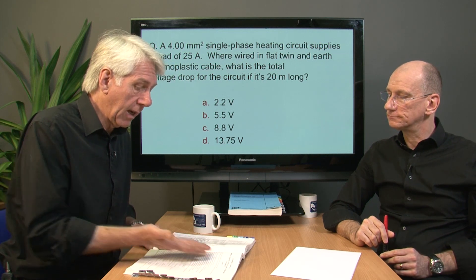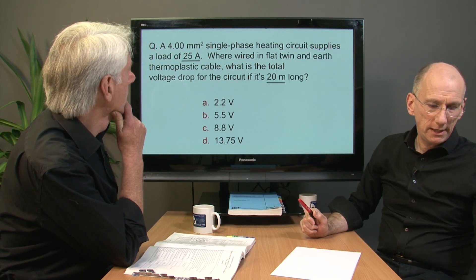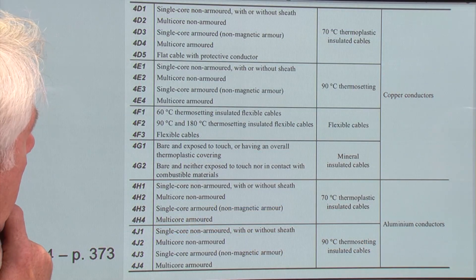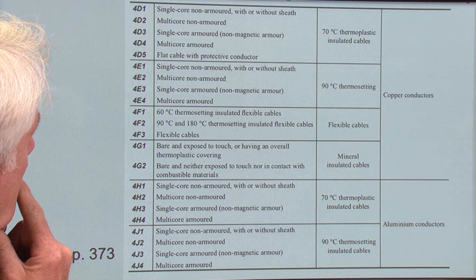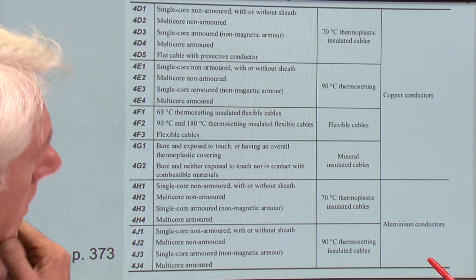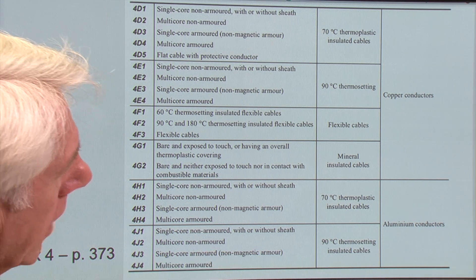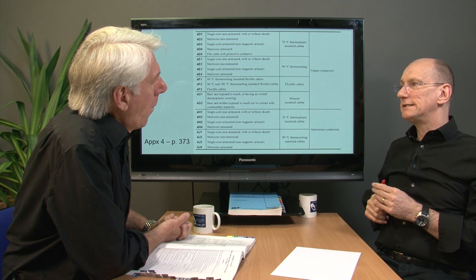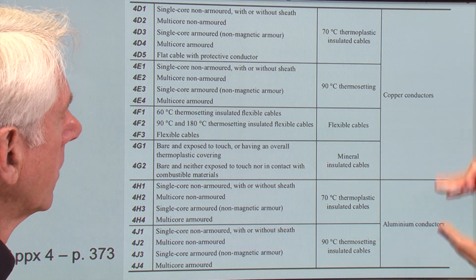Now we've got quite a few tables to consider, so let's take the two bits of information we have: 25 amps and 20 metres. We should also notice what type of cable we've got. The opening page for Appendix 4 is on page 373. It's broken down into aluminium conductors and copper conductors. The question didn't mention what type of conductor it was, but you can't have aluminium cables unless they're 16mm² or above, so we can immediately exclude that. We know we're looking at copper cables, which immediately reduces our choice.